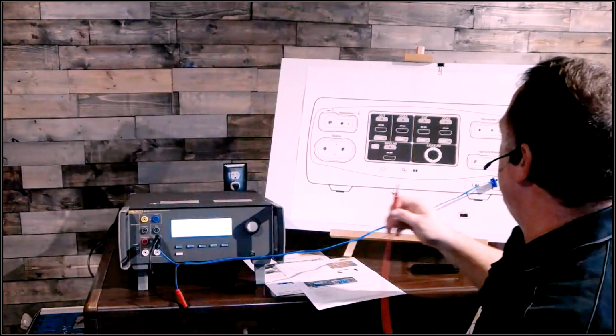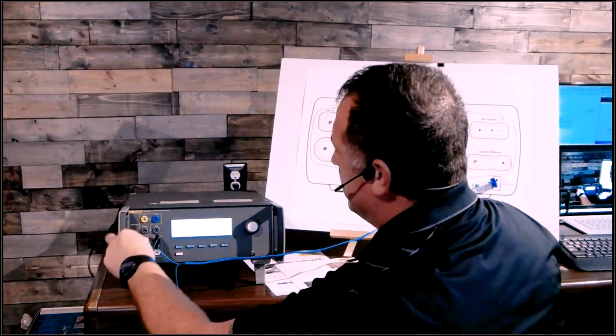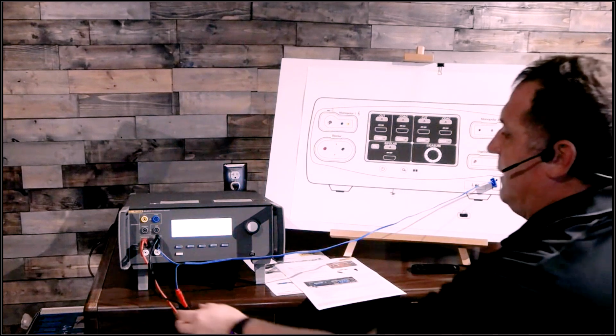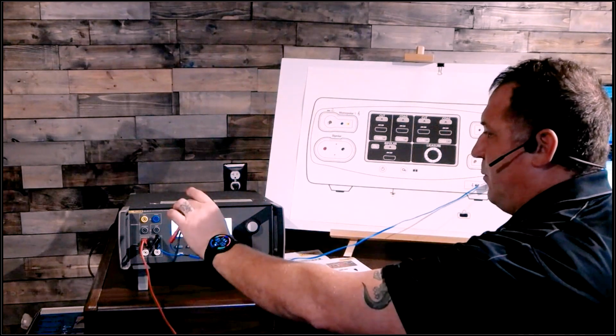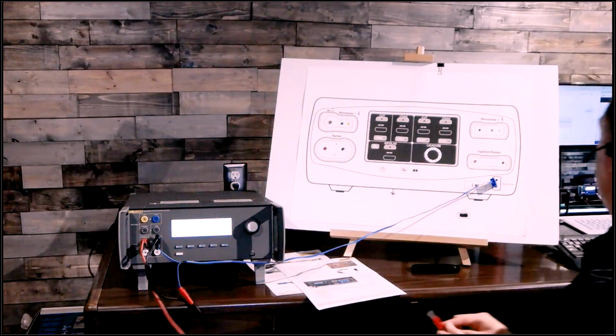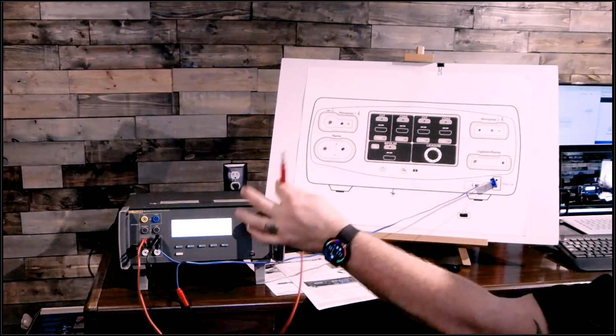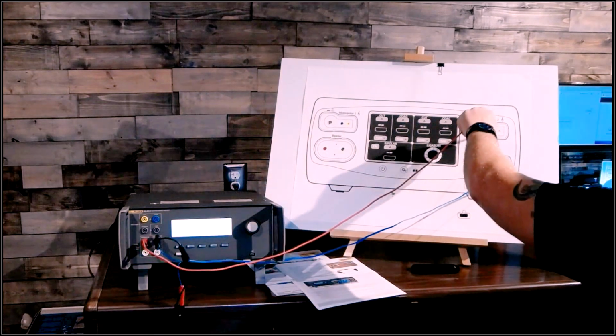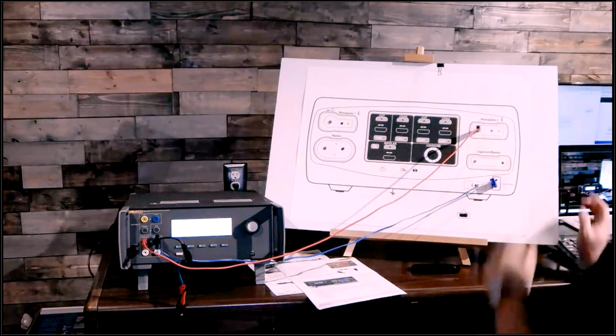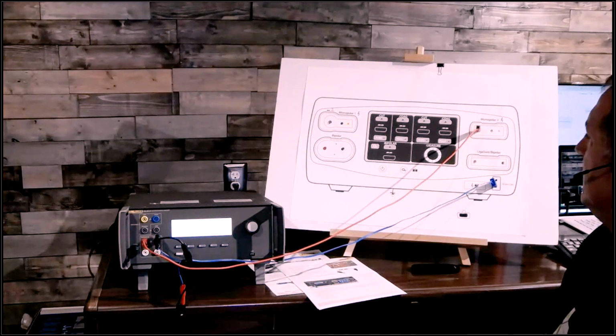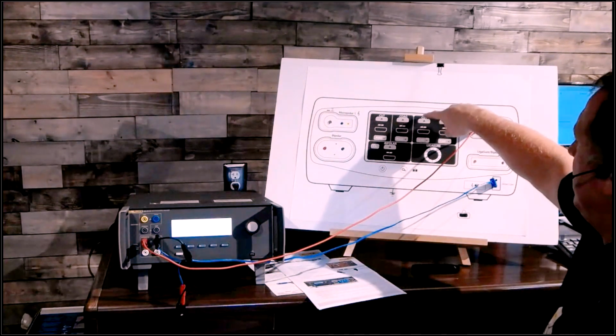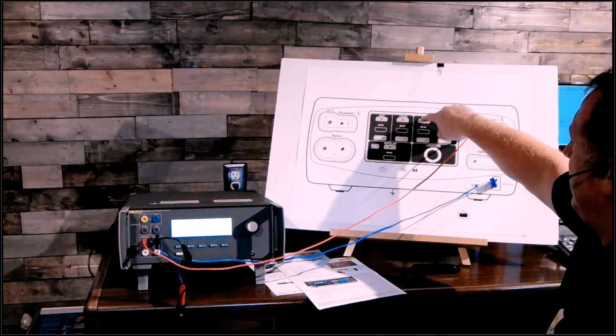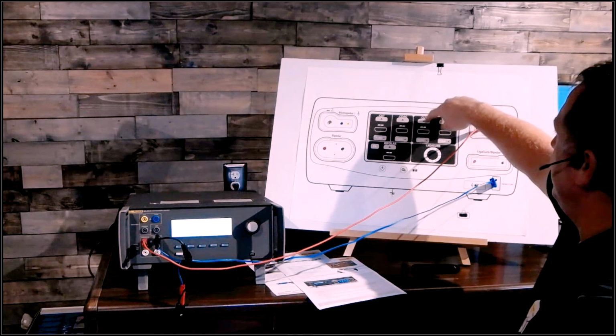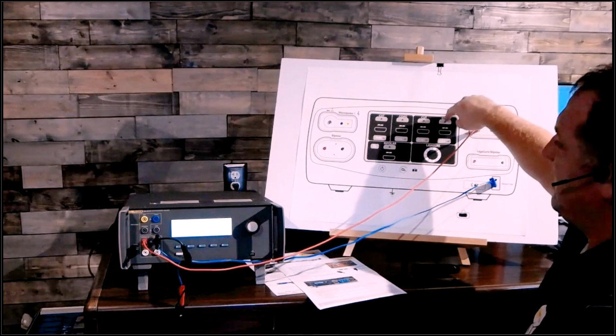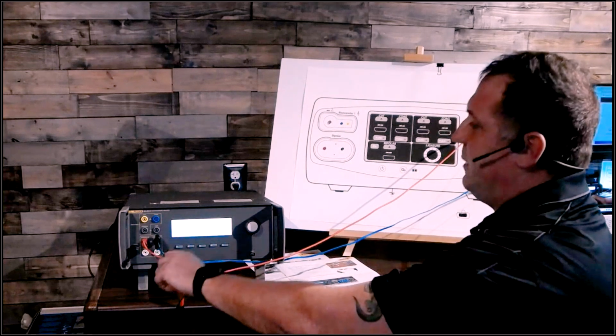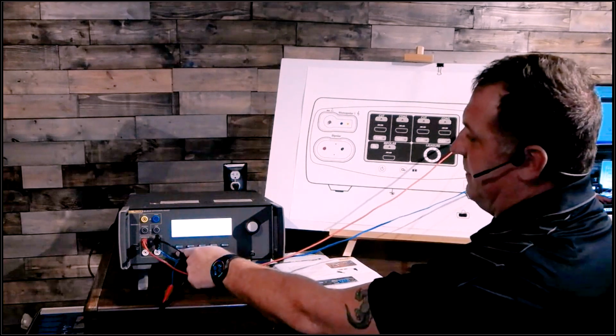So back to my red cable. We're going to go red to red. We have one side of my REM disabling cable connected in the very bottom over here, and I'm going to simply take this red to the port that's by itself in that monopolar connection. That will turn on the ESU. I will now take my cut up to whatever I want to test at, normally max, and my coag the whole way up. Then on my QAS3, since I was in CQM, I'm going to push the back button.